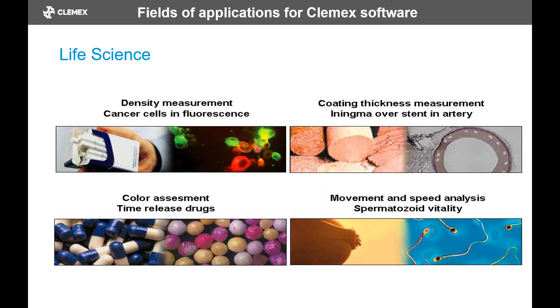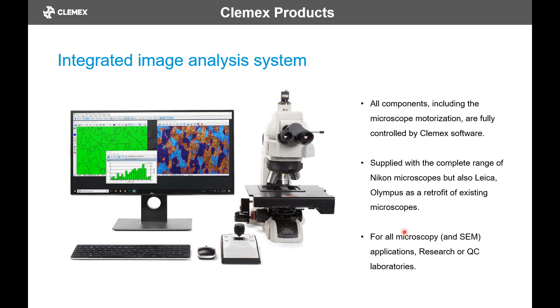Here's an automatic system, while a regular system, where all the components have been integrated. So we control the stage, the camera, the microscope, so the turret would turn automatically, and the light would be controlled so that we can recall a parameter, or a set of parameters, that would be used for specific analysis. So if someone used a microscope in the lab and changed all the parameters, when you use it, it would just come back to the original settings. And we can work with various microscopes. So we have a Nikon and Leica. We can work with Olympus, and we can import images for pretty much anything. So we'll see some of that.